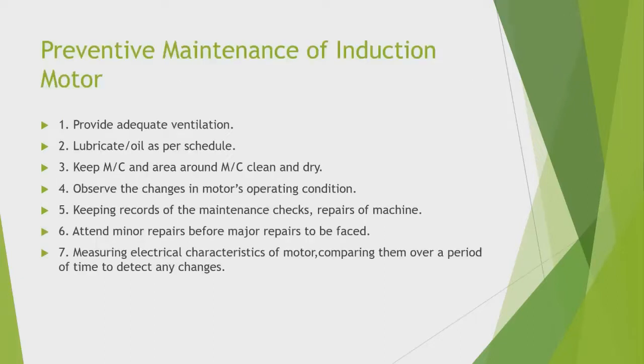Preventive maintenance of induction motor: provide adequate ventilation, lubricate and oil as per schedule, keep the motor and area of motor clean and dry, observe changes in motor operating conditions, keep records of maintenance checks and repairs, and attend to minor repairs before they become major repairs. Measure electrical characteristics of the motor and compare them over a period of time to detect any changes.